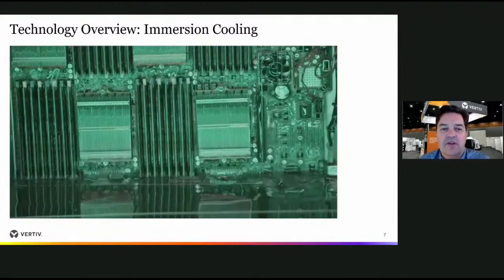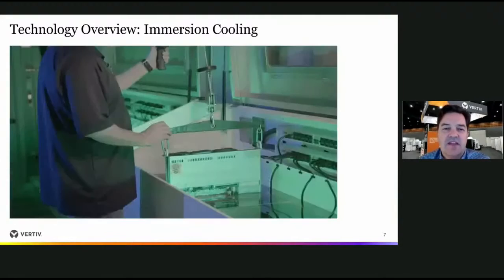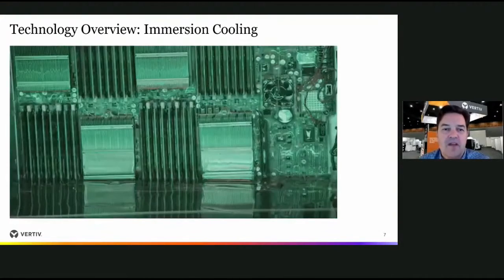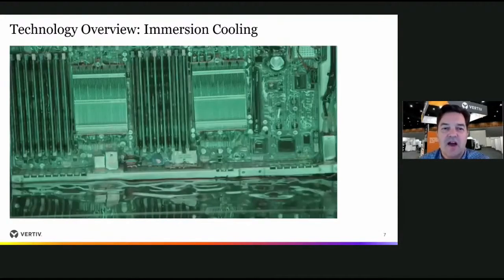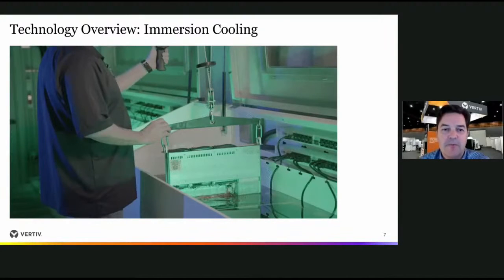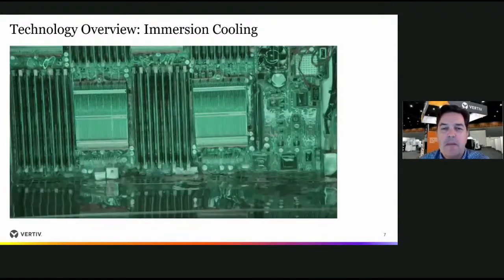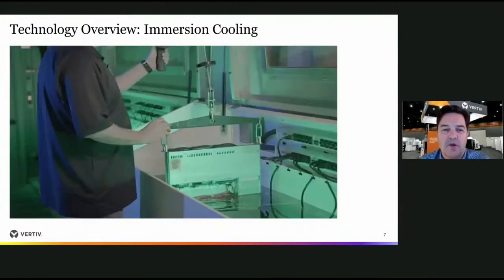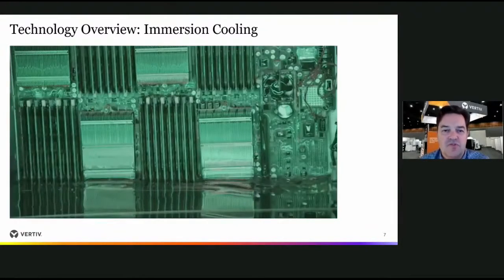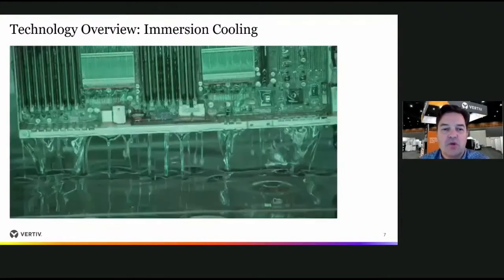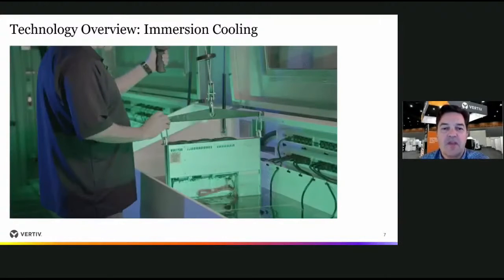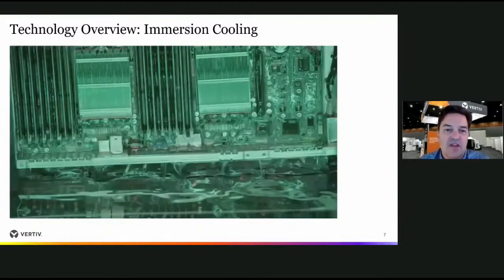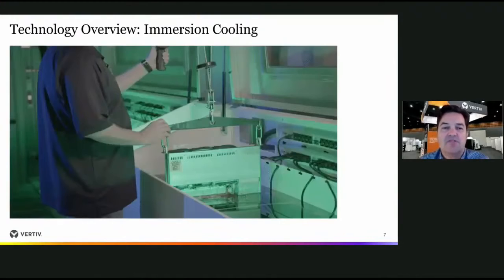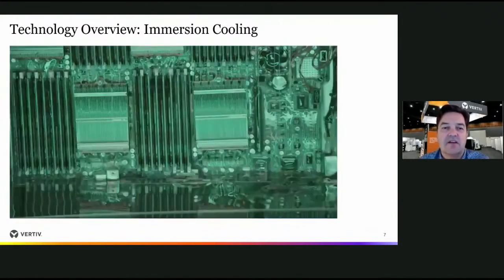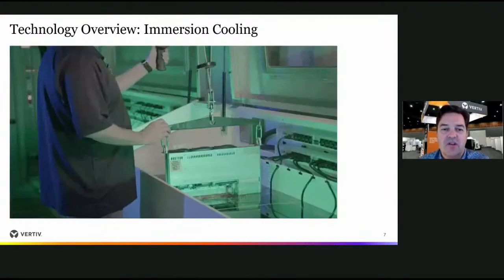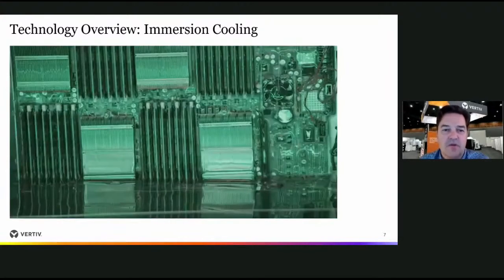Second, when you see the server being removed from the tank, you notice how the oil, the liquid, the fluid is touching every single component within the server—the main high heat components such as the CPU, memory, hard drive, but even the smaller components, the ICs, the voltage regulators, all the small components on the server mainboard. This is one of the best value propositions immersion cooling offers, because it's able to cover the entire server system, giving you 100% heat to liquid.